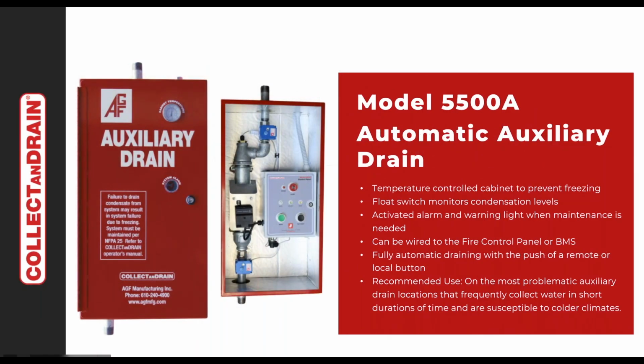So then our last evolution is a fully electronic self-draining low point drain. And this one offers a variety of features such as semi-automatic mode, so it can be initiated for draining by just simply pushing a button. It can be put into full automatic mode, and so when the unit senses it's nearly full, it will close itself off from the system to maintain system air integrity. And then once it senses that it is closed, it will then open its bottom drain and drain all of the accumulated water out. Once it senses it's empty, it will then reset itself.